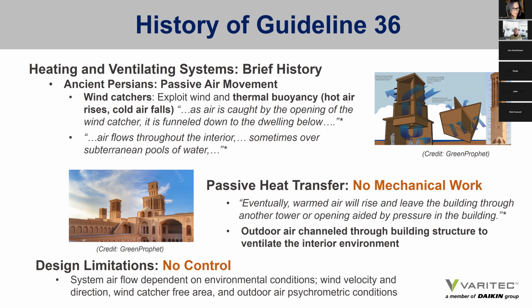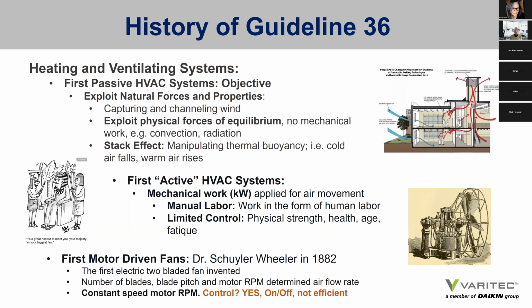So you had a continual flow of air through the space. There was no mechanical work to do that. It just happened by nature. The problem is with that design that though effective when the wind was blowing, at least up to a certain level, there was no control. You got what you got. System airflow was dependent on the environmental conditions, wind velocity and direction, and the wind catcher free area available to the wind, as well as outdoor psychrometric conditions. So the first passive HVAC systems exploited the natural forces of physics and properties by capturing and channeling wind and exploiting variations of air pressure.